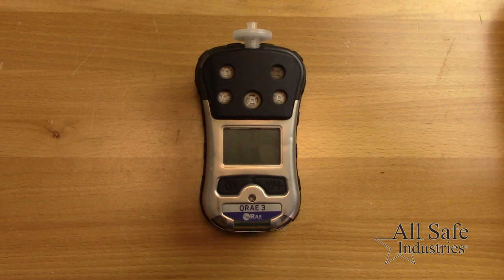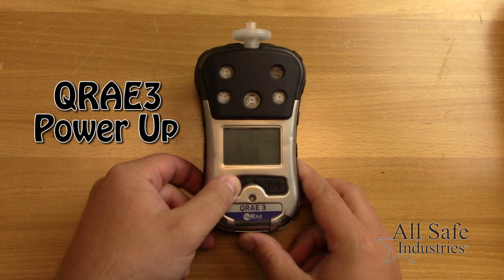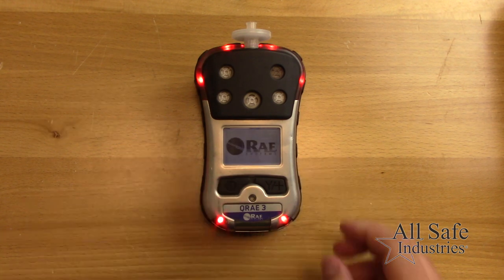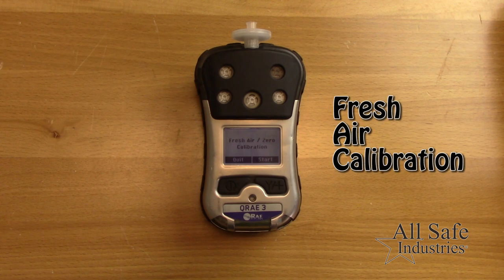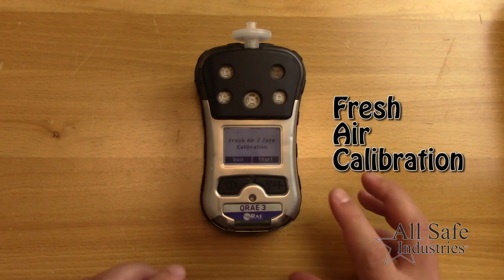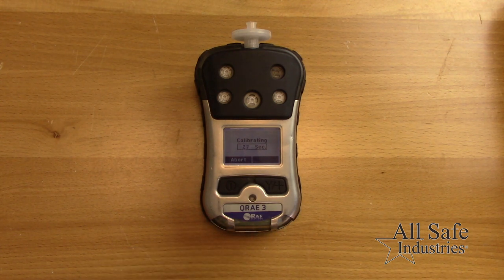This quick video will show you basic operation for the QRAE3. To power up the meter, press and hold the left button until you hear the meter beep. After the warm-up, you'll be prompted to perform a fresh air zero calibration. Ensure you are in a clean fresh air environment and press the Y-plus key to start.